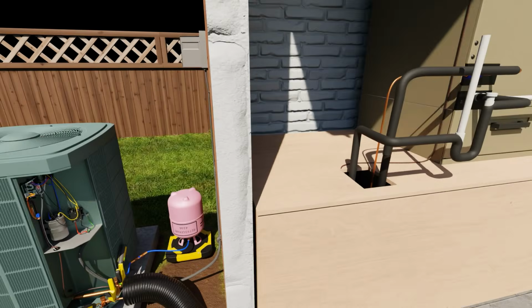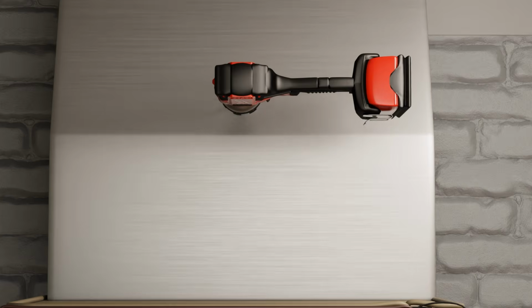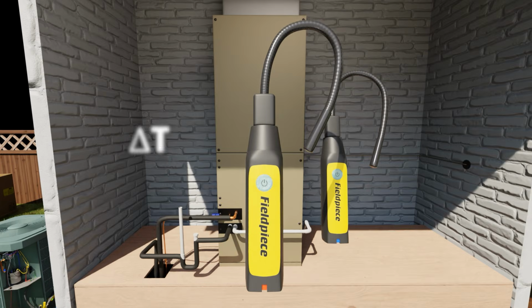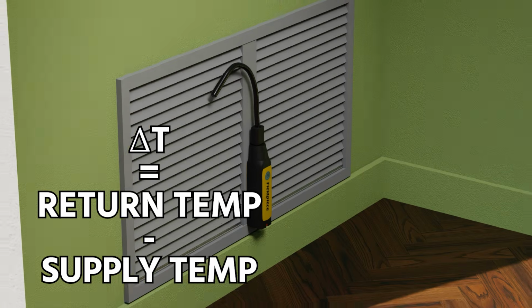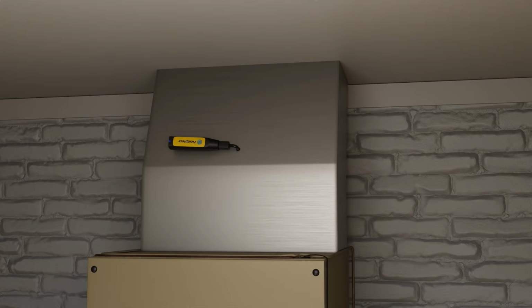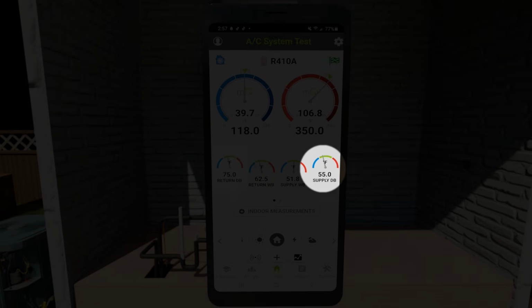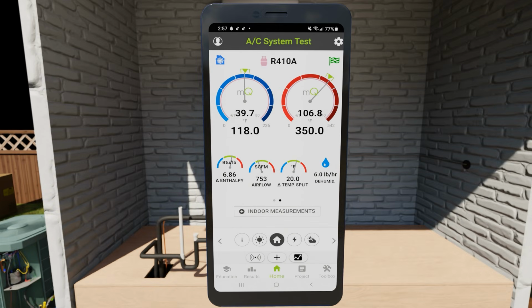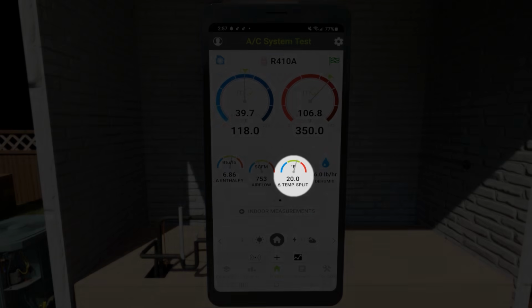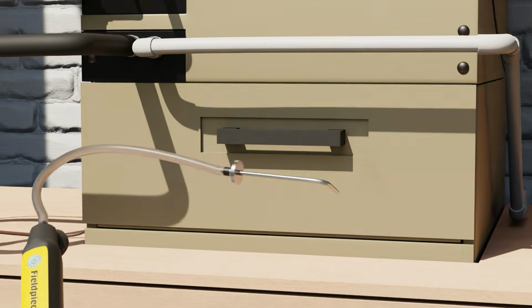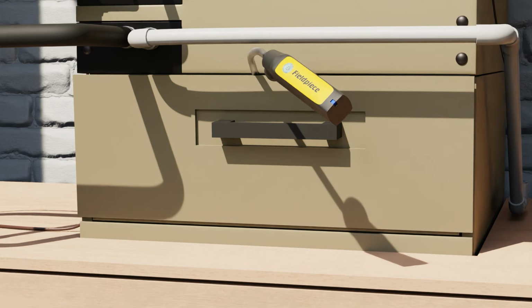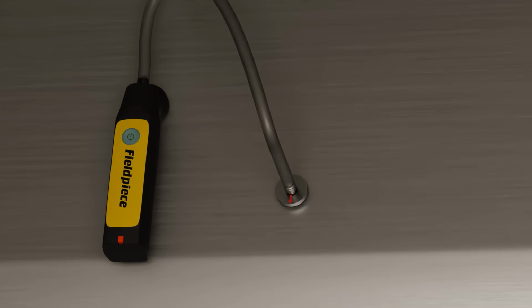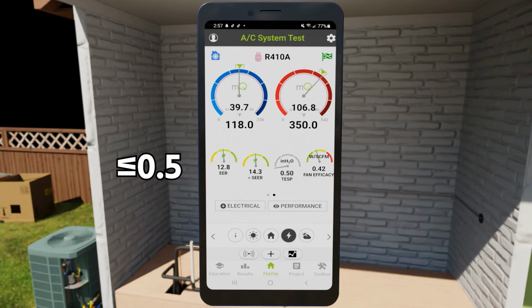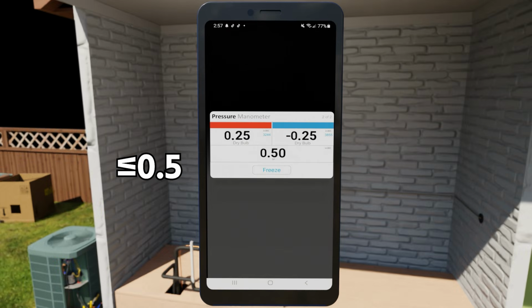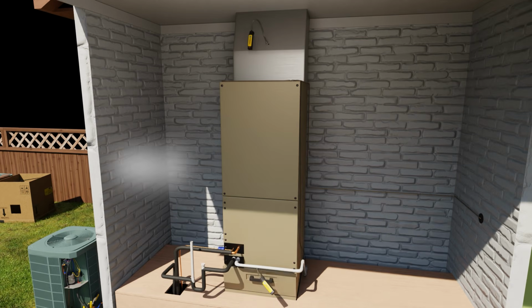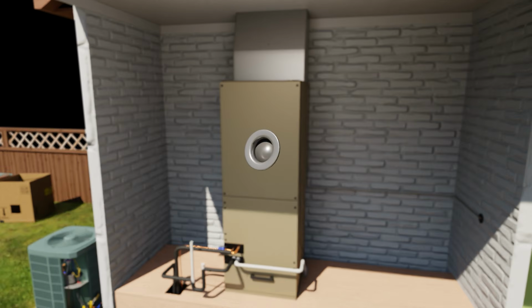Now we're going to quickly show how we would use digital psychrometers, one on the return and one on the supply duct, in order to monitor the delta T, which is the difference between the return and supply temperature. We're using MeasureQuick, and you can see that we're in the green zone at 20 degrees for this particular situation, which is what we're looking for. Now we're going to use manometers in both the return and the supply in order to measure our total external static pressure. Generally speaking, for these types of systems, a total external static of 0.5 or lower is what we're looking for, but you need to look at the design literature to see what's appropriate in your application.